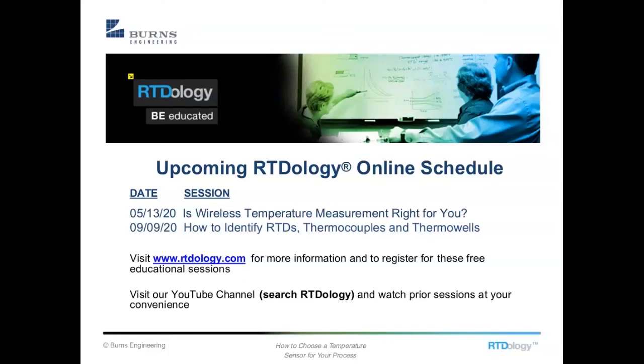Yeah, now that's going to vary a little bit. It goes anywhere from, if you just want a 0 degrees C check, maybe a $10 or $15 item, on up to over $600 for a system calibration where we're doing a below-to-above-zero calibration on a temperature probe and matching it to a readout. So there are various levels in between. Like I said, it could vary quite a bit. We can certainly help you out with that, and if you have something specific in mind, we can certainly address that.